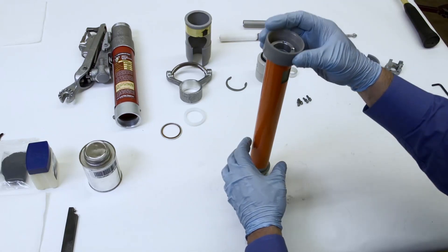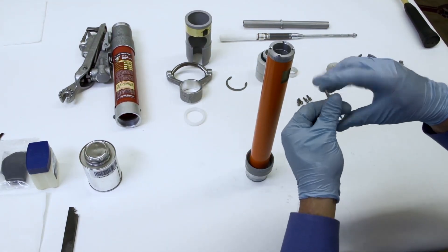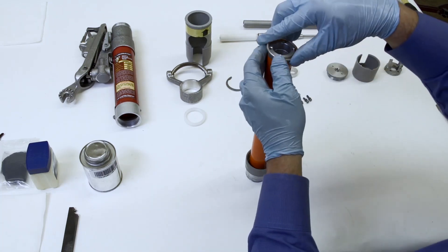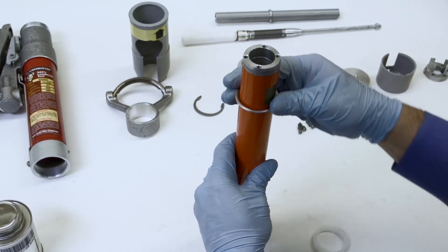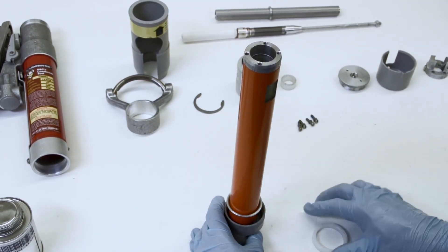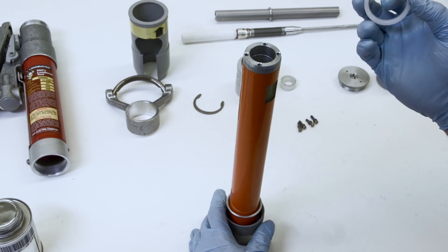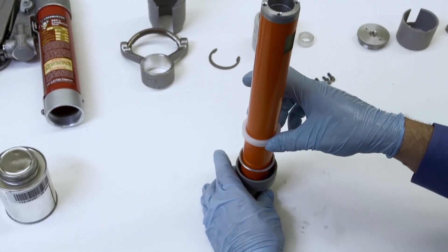Then slide the bearing retainer onto the inner tube assembly, followed by the inner tube seal. Make sure the flared edge is pointing toward the stationary contact. Use care to avoid damaging the seal. Using a twisting motion, work the inner tube seal onto the inner tube assembly. Use care going over the latch notch on the inner tube assembly. Then slide the bearing on the inner tube assembly.